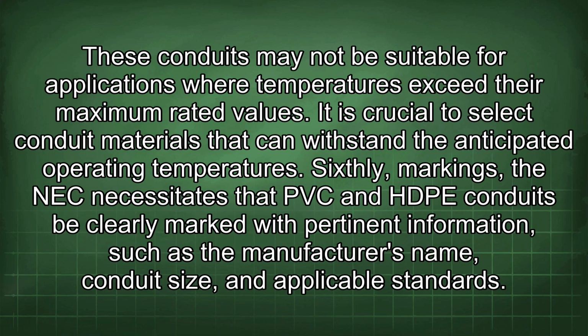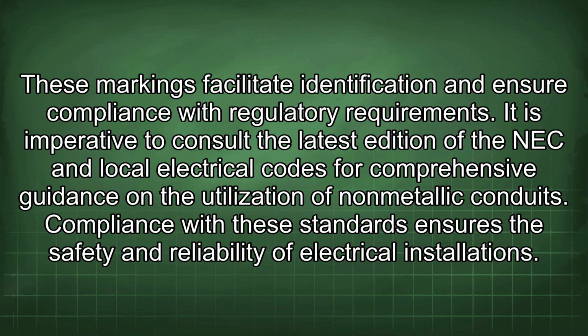These conduits may not be suitable for applications where temperatures exceed their maximum rated values. It is crucial to select conduit materials that can withstand the anticipated operating temperatures. Sixthly, markings. The NEC necessitates that PVC and HDPE conduits be clearly marked with pertinent information, such as the manufacturer's name, conduit size, and applicable standards.